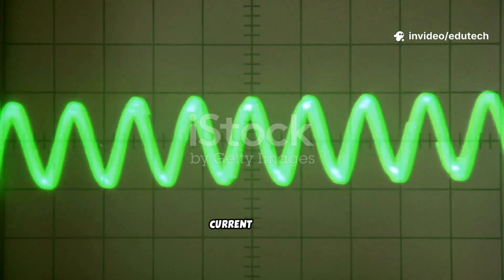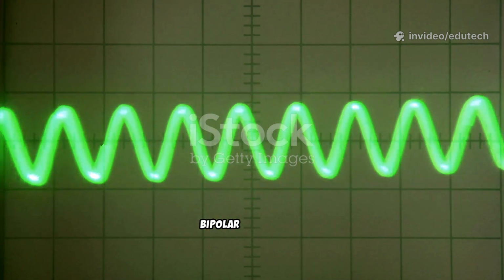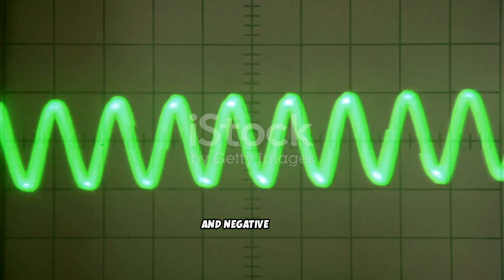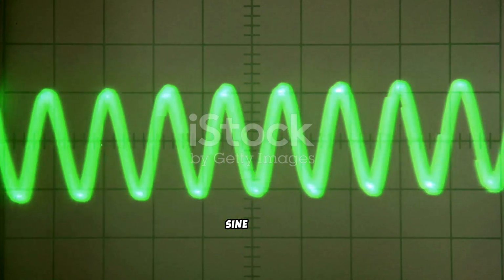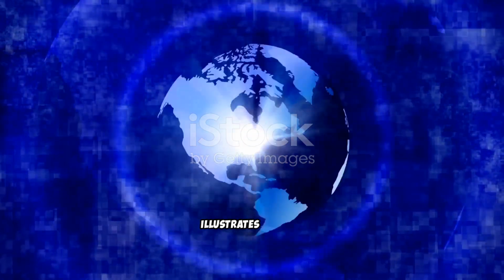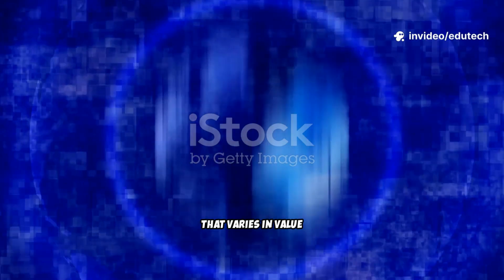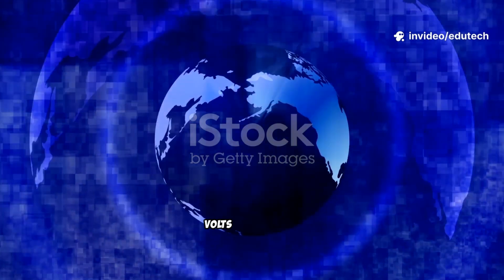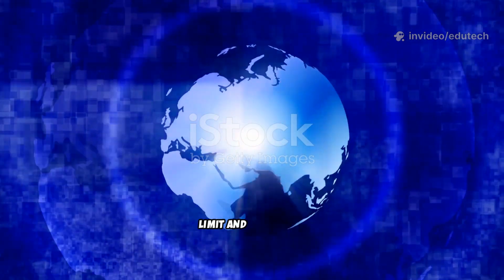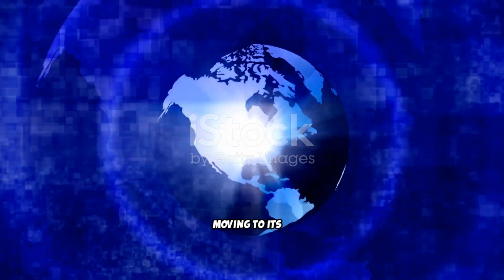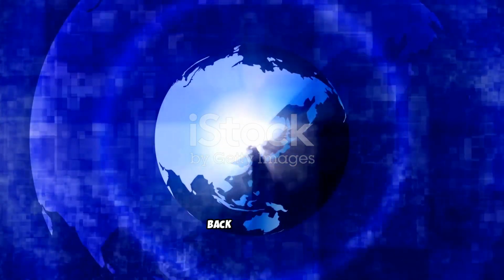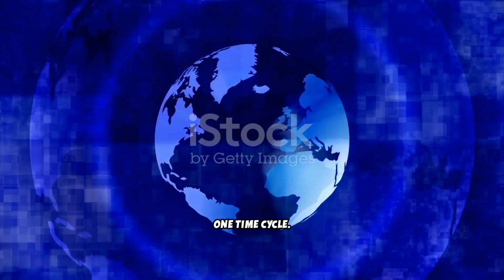AC, alternating current analog signals, can be bipolar in that they have both positive and negative limits, as seen in an AC sine wave. Figure 3.1 illustrates the sine wave output of an AC synchro transmitter that varies in value, amplitude, from 0 volts to its plus 5 volt limit and returns to 0 volts before moving to its minus 5 volt limit and then back to 0 volts in one time cycle.